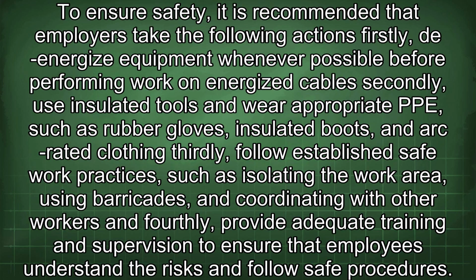To ensure safety, it is recommended that employers take the following actions. Firstly, de-energize equipment whenever possible before performing work on energized cables. Secondly, use insulated tools and wear appropriate PPE such as rubber gloves, insulated boots, and arc-rated clothing. Thirdly, follow established safe work practices such as isolating the work area, using barricades, and coordinating with other workers. And fourthly, provide adequate training and supervision to ensure that employees understand the risks and follow safe procedures.